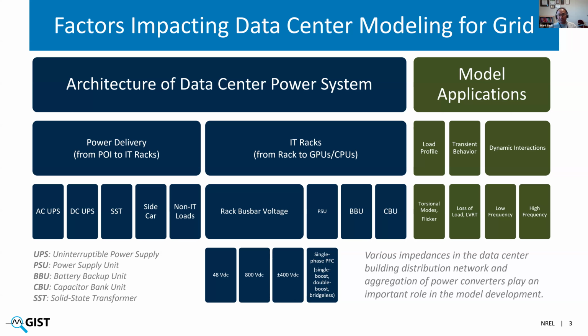The other part we need to consider is the architecture of the data center. There are two parts: power delivery from POI to IT racks, and what is inside the IT racks. Within power delivery, AC UPS is the one power electronics converter we all talk about. There's also talk about having a DC UPS to reduce conversion stages, a solid state transformer, or a sidecar where you put all the power supplies outside of the IT rack in a different rack, to have enough room within the IT rack for GPUs, CPUs, server nodes, and non-IT load. So there are many variations that we should be mindful of.